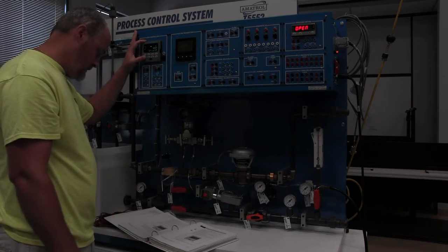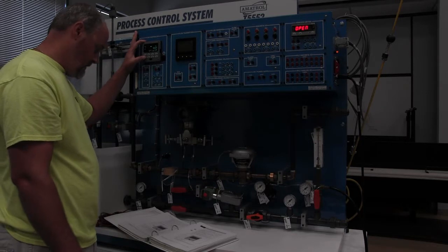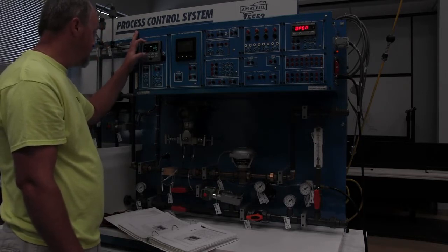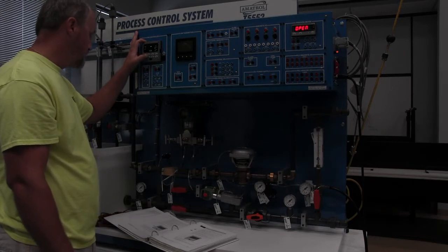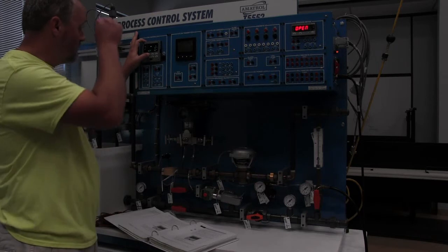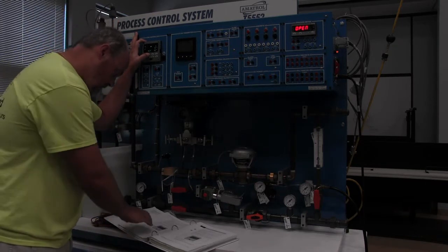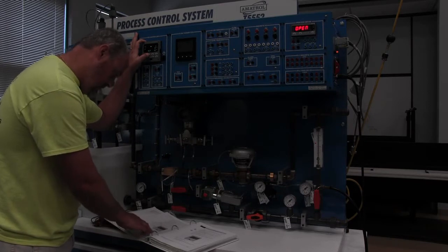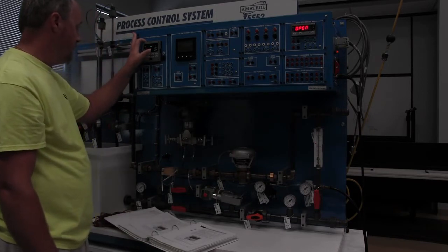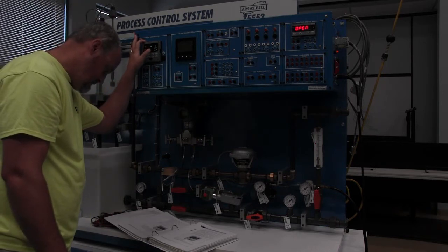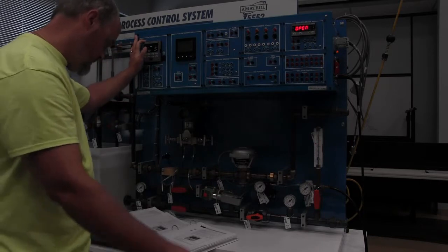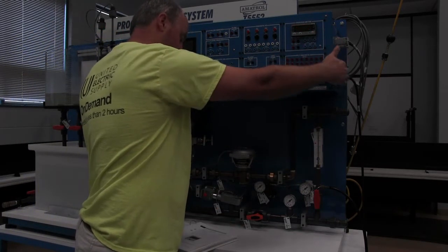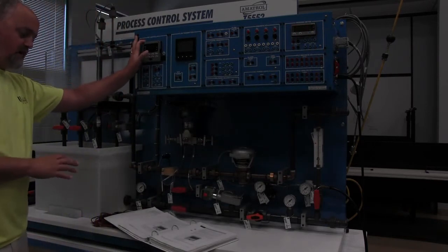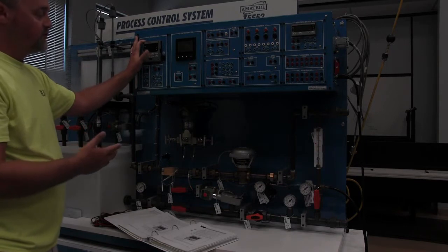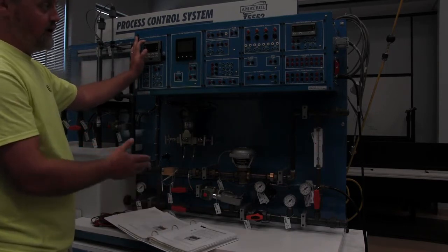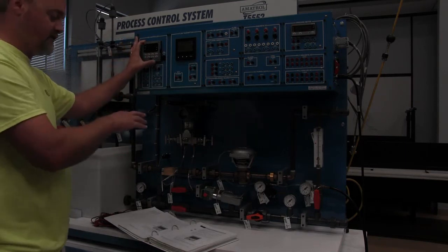So continue to press the lower display key until we see set SP. We see set point. Use the up and down arrow keys to a value of 15. We're now set point at 15. Turn off the main circuit breaker and shut down the trainer. So it made us change those parameters for no other purpose other than we're now going to reset the controller. And by resetting the controller, it's going to take everything in it back to factory.